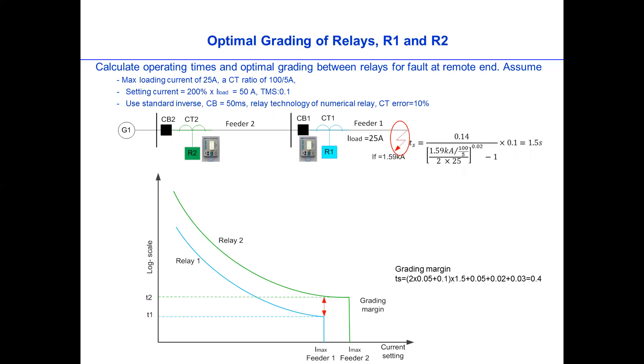For example, we can just use this kind of formula, the standard inverse, 0.14, 1.59 kAmps, which is the fault current, divided by the CT ratio, divided by the setting current. And if we use TMS value, which is the minimum value of 0.1, then we have a trip time of 1.5 seconds. So the T1 will be 1.5 seconds.